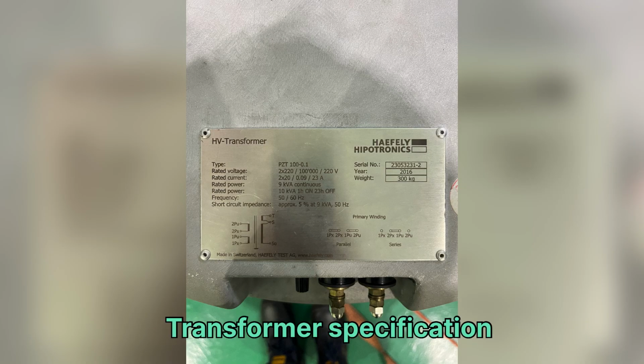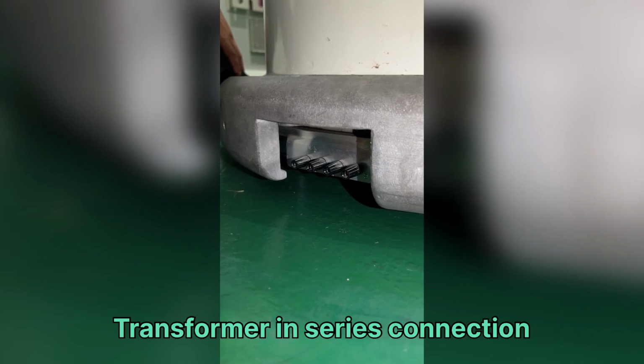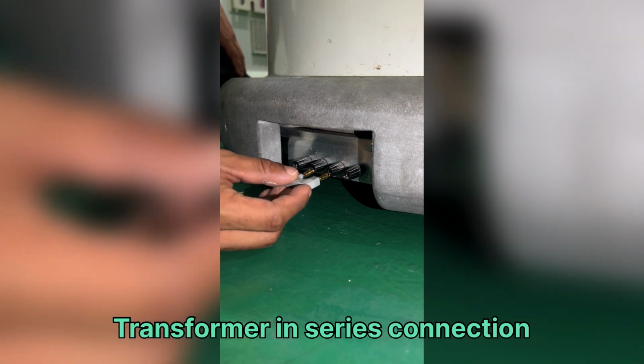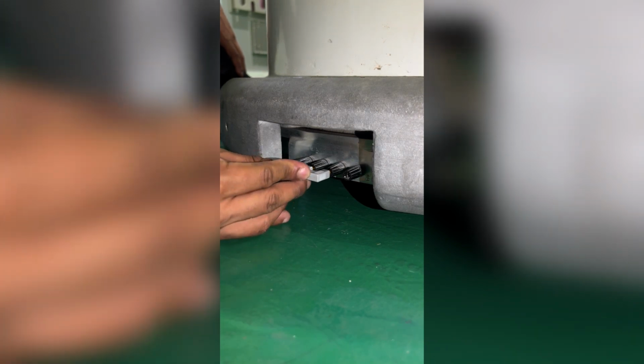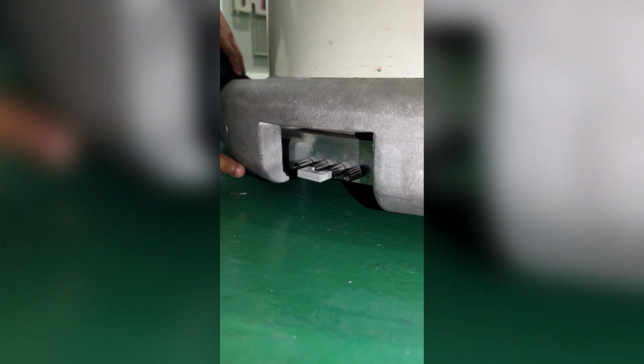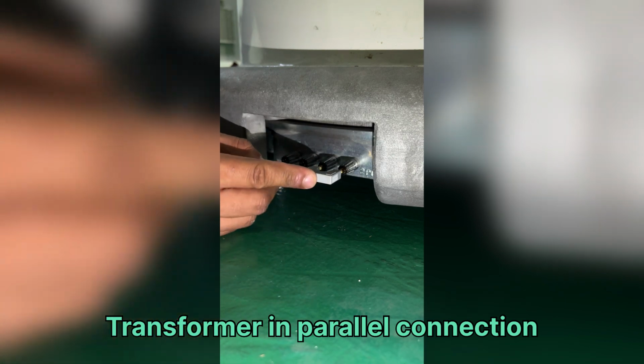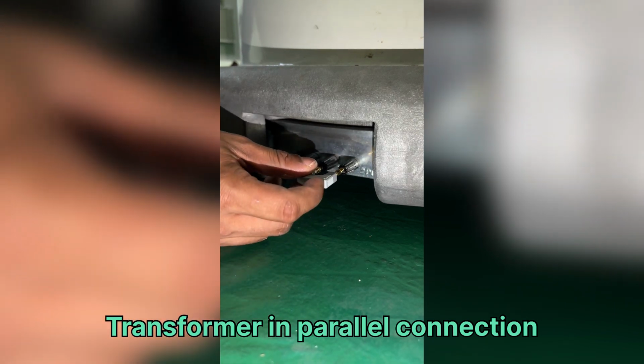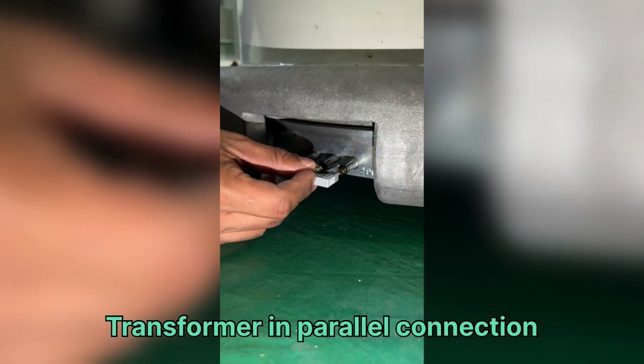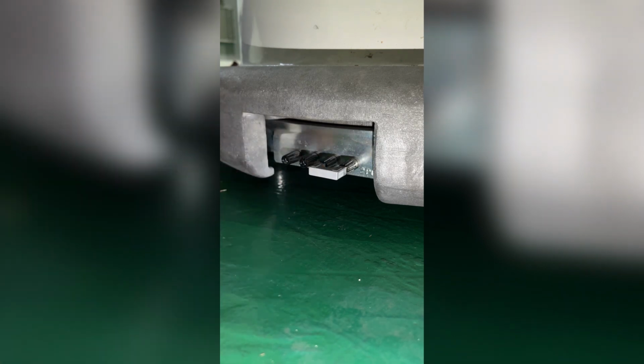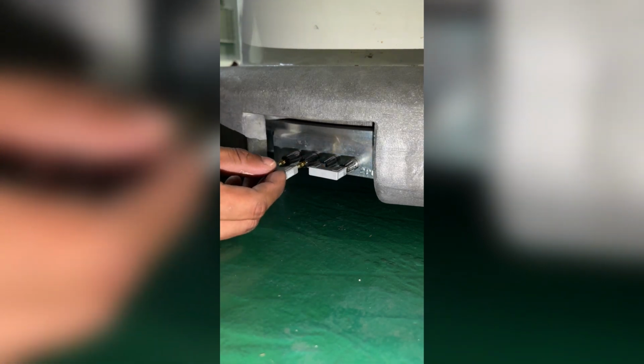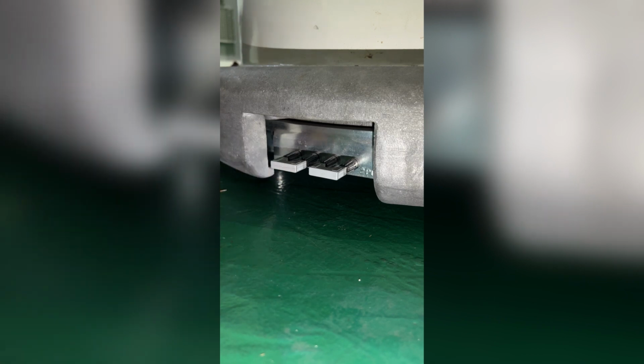The last one is identify the transformer specification and connection. S0 is the beginning of the secondary winding, S is the high voltage end of the secondary winding, and T is the end of the tertiary winding. The low voltage winding of the transformer consists of two winding groups, which could be connected either in series or in parallel. For cascade operation of the transformer with the kit FU, the two winding groups should be connected in series.